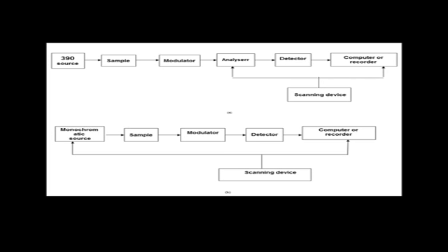In the microwave and radio frequency ranges, monochromatic sources whose emission frequency can be varied over a range are selected. The figure shows no analyzer is necessary, the source being in a sense its own analyzer. Now, it is necessary for the recorder to be synchronized with the source scanning device in order that a spectral trace be obtained. This is the typical diagram of a scanning absorption spectrophotometer.